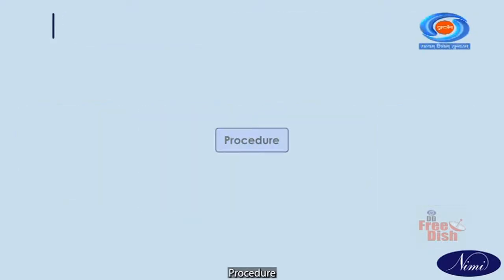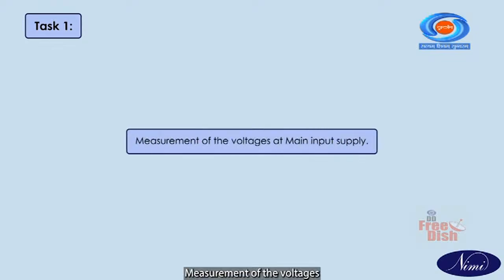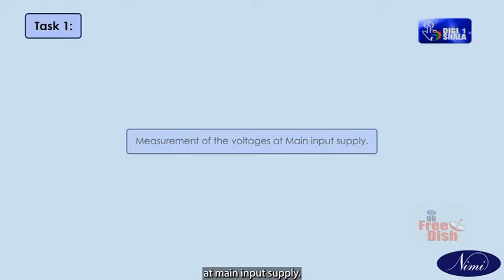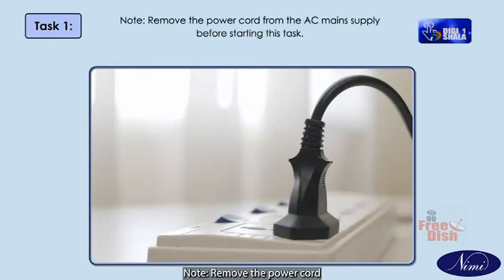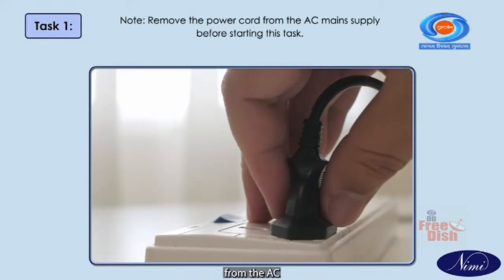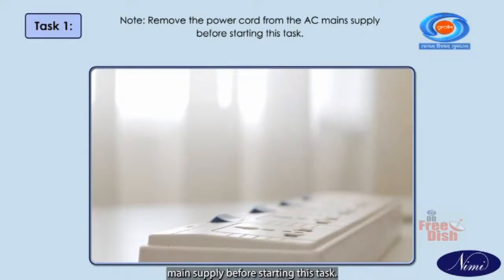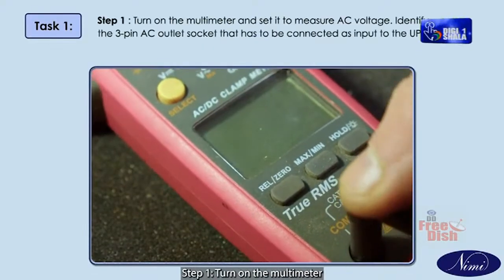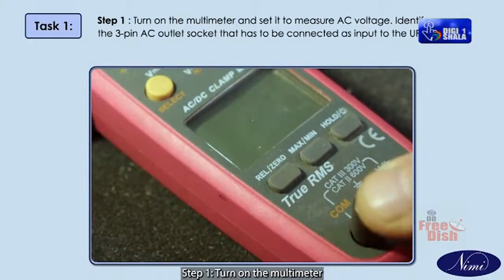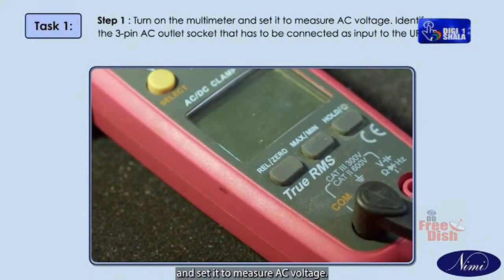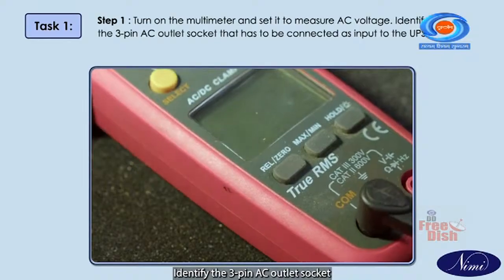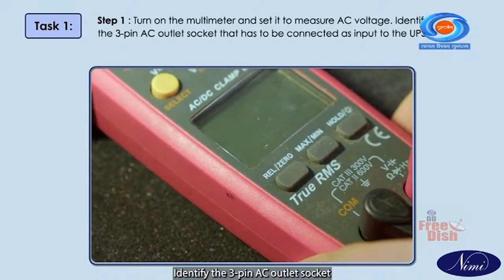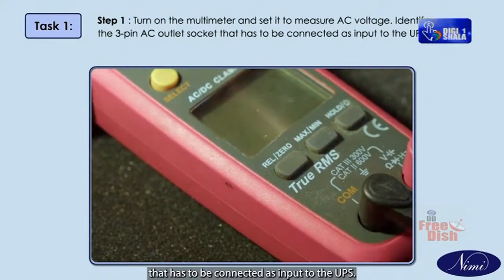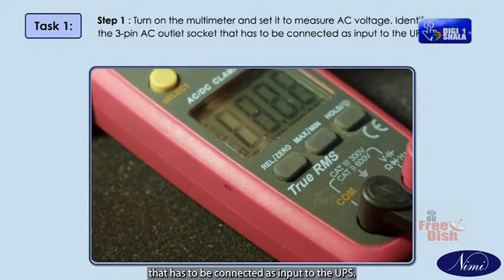Procedure. Task 1. Measurement of the voltages at main input supply. Note: remove the power cord from the AC main supply before starting this task. Step 1. Turn on the multimeter and set it to measure AC voltage. Identify the 3-pin AC outlet socket that has to be connected as input to the UPS.